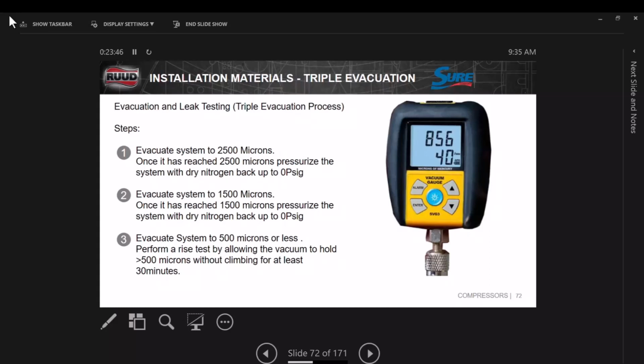Now, if we just take a typical system where we live today, and it could be a morning like it was this morning, real foggy outside, that means there's a lot of moisture in the air, right? And all the moisture is right here where you're working. And we pull this thing down to 500 microns and think we have it good. We shut our valves off, and guess what? Pressures come up, right? We think we got a leak. In reality, we have moisture in the system.